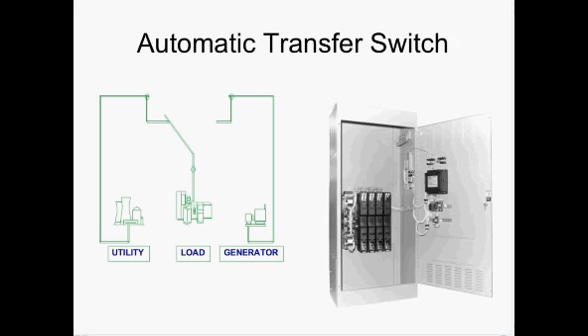Two main failures for emergency generator sets are starting batteries that are dead or an insufficient fuel supply in the tank. Both of these issues can be avoided with a weekly inspection of the emergency power system. Municipalities are big customers for emergency power systems with diesel engine-driven generator sets. Most of us like the water supply to be uninterrupted as well as the electric power. It is good to have the sewer system working as well. There is no engine generator set customer more upset than the city manager who has to explain to the homeowners why the sewage lift pumps did not operate. Guess what backs up into the basement drains and toilets of the homeowner? Reliable backup power at the lift station can avoid this unhappy experience. Here's an example of a diesel engine generator set installed at a municipal sewage lift station.